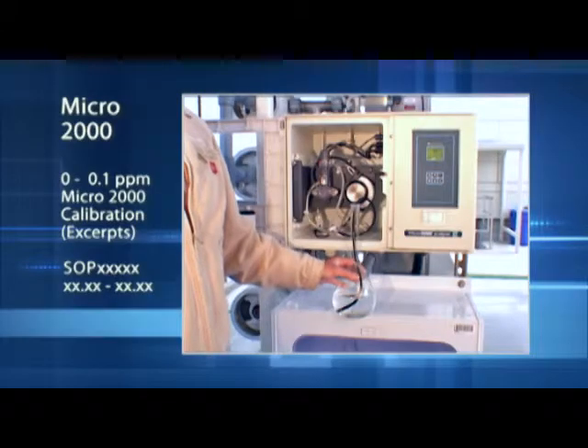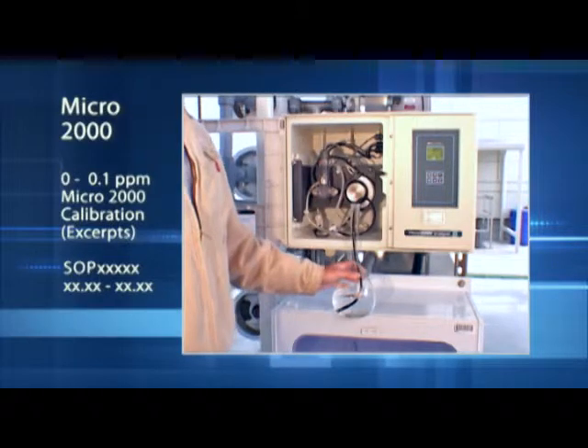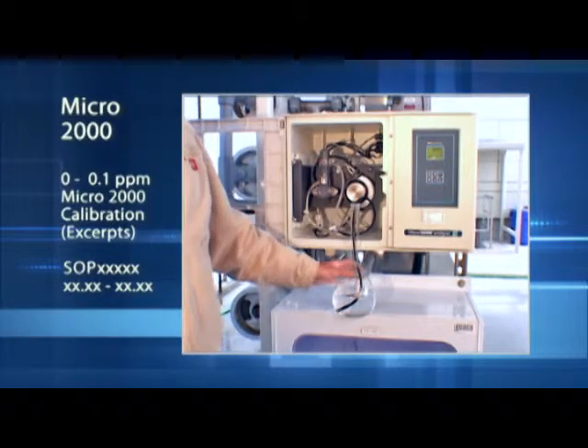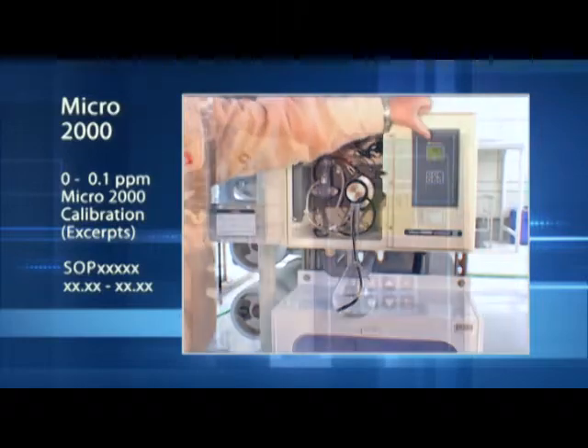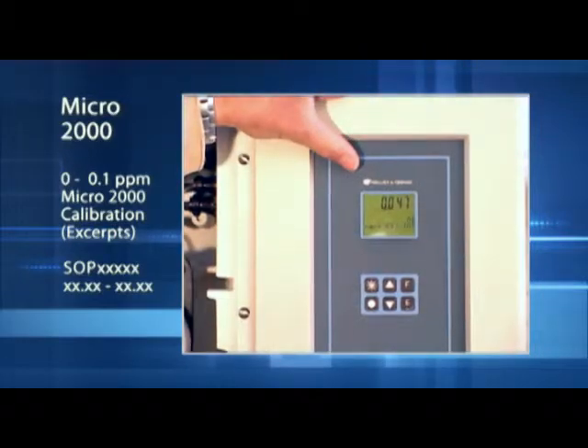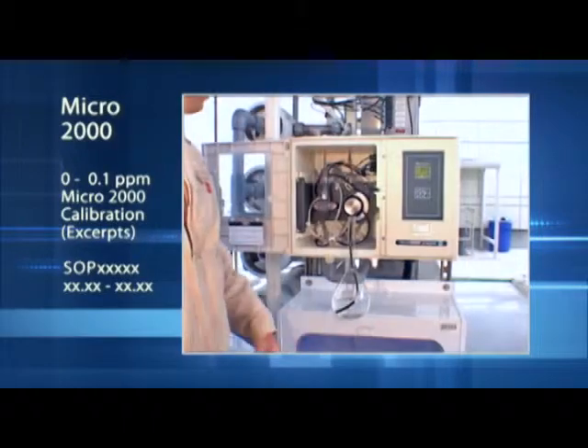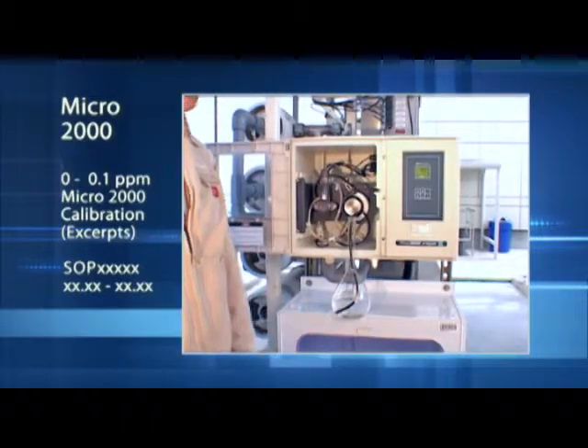So at this point, the sample's been sitting here for 15 minutes, and we should be reading 0.070 ppm, and we are maxed out at 0.047 ppm. So at this point, we will repeat the test to verify accuracy of the sample.